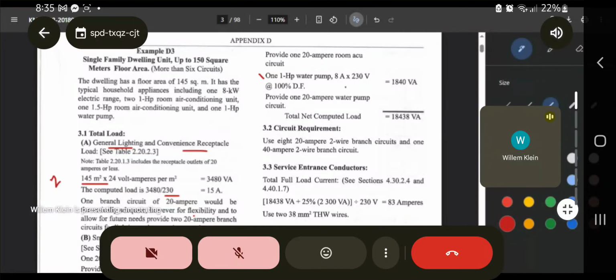That's the usual rating for a 1 HP water pump. No, so that's also mentioned in the tables, so that you can directly use this as reference. So no need to look for the table. Okay. So 1 HP usually that's 8 amperes, 230 volts. So that's 1840 VA, 100% demand factor. Okay. So you'll also use a 20 ampere circuit.